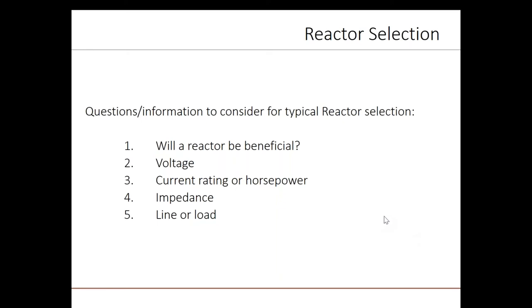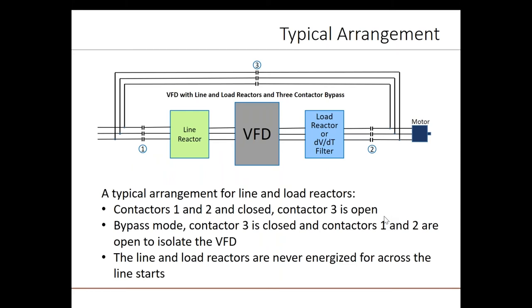Let's start with whether the reactor will provide a benefit. As we discuss line and load reactors, we'll refer back to this diagram. This represents a typical VFD with line and load reactors, and also shown in the schematic are a classic three-contactor bypass arrangement. The line and load reactors are not in the circuit for bypass operation, since they are designed to address issues caused by the VFD, and are not designed for the higher motor inrush that is typical with bypass operation when you start the motor across the line.